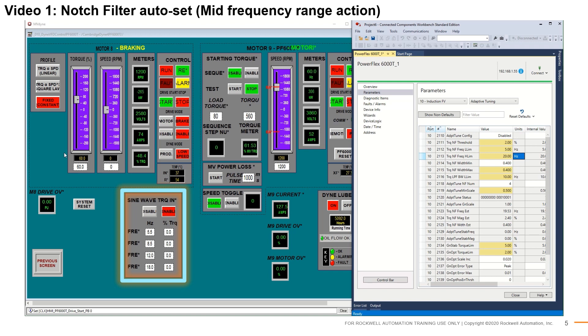The drive is currently operational and a constant load has been applied. The sinusoidal load injections following this will be superimposed on this constant load level. Before the start of this video, adaptive tuning has been configured to match the intended frequency range of injections. See that with the feature off, the notch filters have not yet been automatically set.